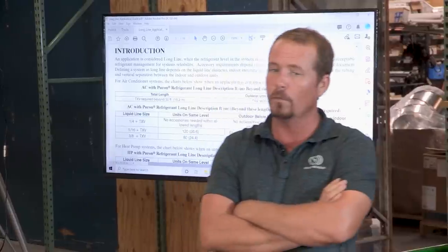The suction line, right? And what is the coldest part of the system now if you have a buried suction line? The suction line. So where is liquid refrigerant going to condense? The condenser? That's what it's for. When the system is off, it's going to condense in the suction line. So what's going to happen when it's off for a while and then it comes back on? Liquid is going to be sucked into that compressor, right? So we do it all the time.